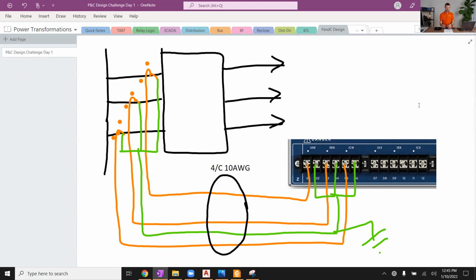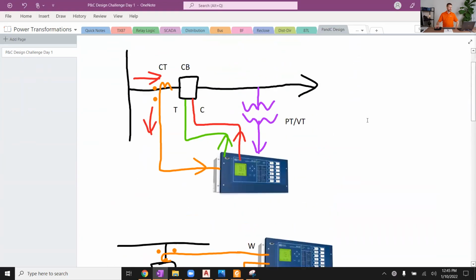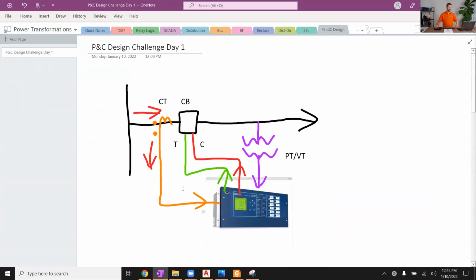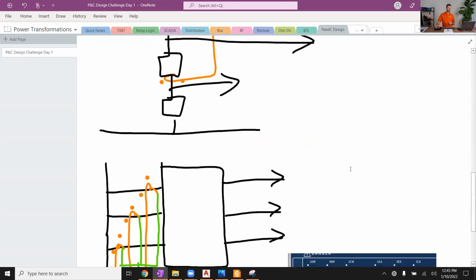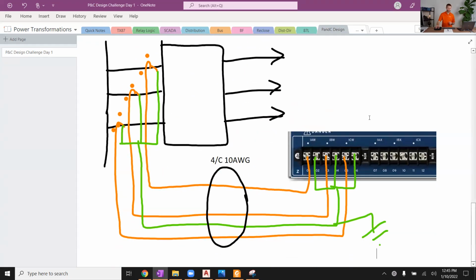I want to point out one other thing about these neutrals though. Notice over here on our one lines, I did not draw the neutral wire on the CT. And that was intentional. We typically do not include the neutrals on a one line. It just starts to get too cluttered and too many lines to keep track of. This is simple, but when you start to get to 10 or more breakers and relays in the equation, you got lots of lines going around. So we typically just leave off the neutral from the one line drawing, but we will show it on the 3-line drawing. We're going to look at actual examples of these tomorrow, but hopefully you're grasping these concepts today.